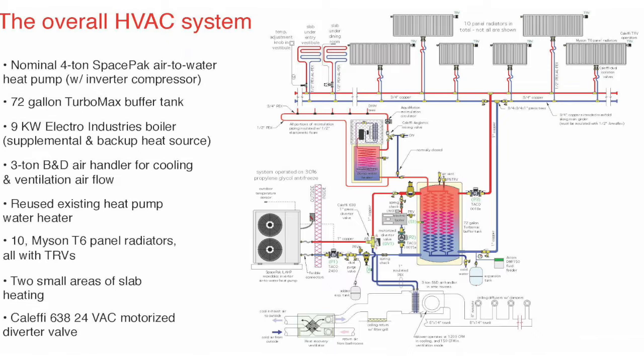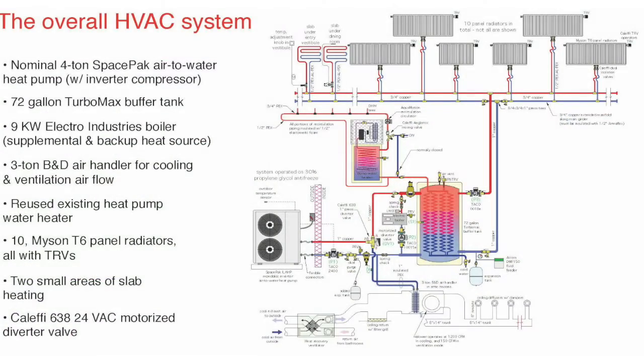Now, again, these are all non-electric thermostatic radiator valves. You might be wondering, how did you control the radiant floor circuits? Well, we use non-electric thermostatic radiator valves. You can buy these valves with a device that screws on the top of the valve like a TRV, but it goes to a capillary tube, and the capillary tube goes up the wall, and there's a wall-mounted control for it. So you can adjust the 1 to 5 range, just like you would on a standard knob on the panel rad. So there's actually 12 different zones, all controlled by thermostatic radiator valves in the system.